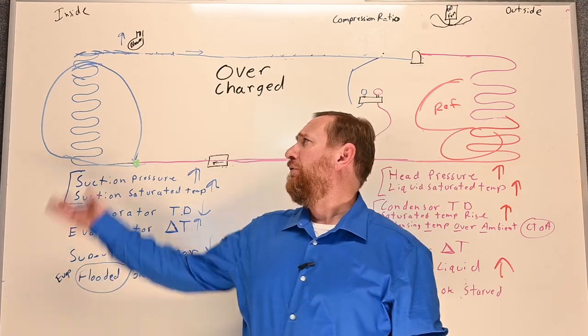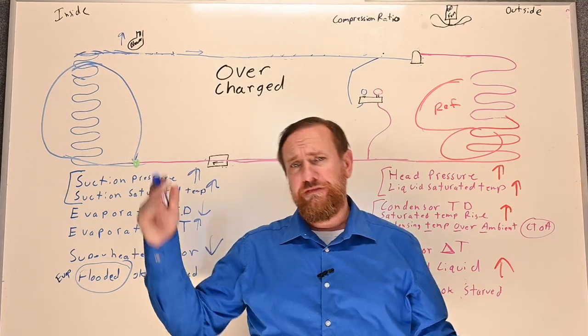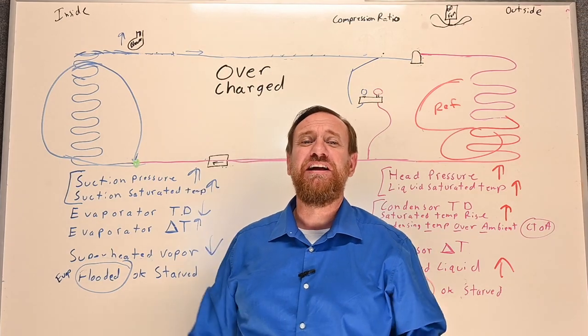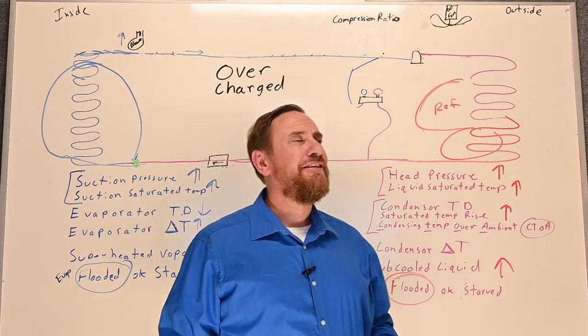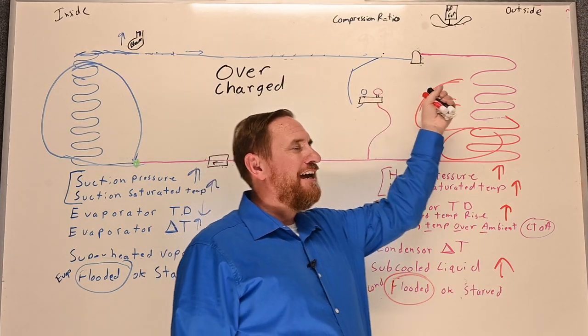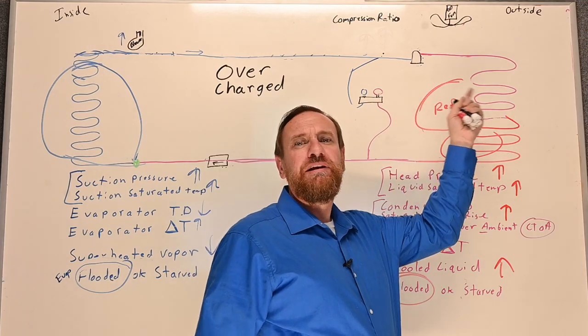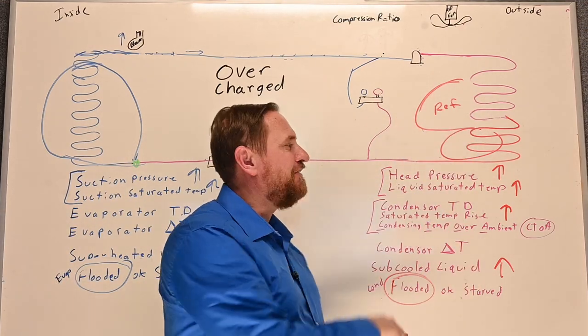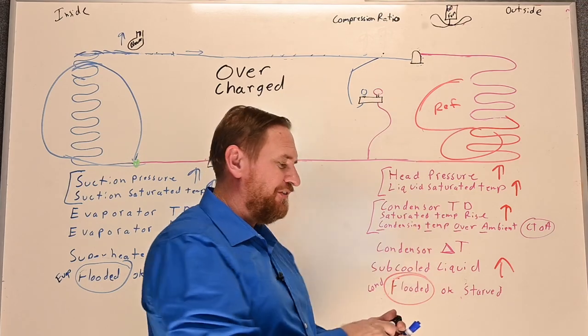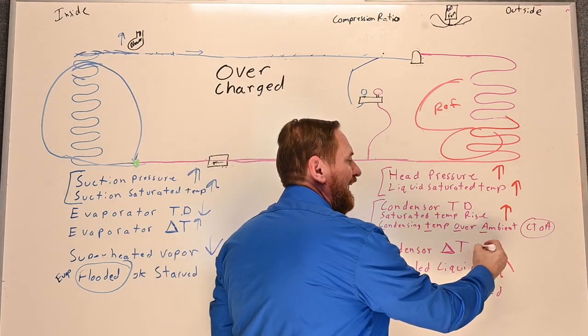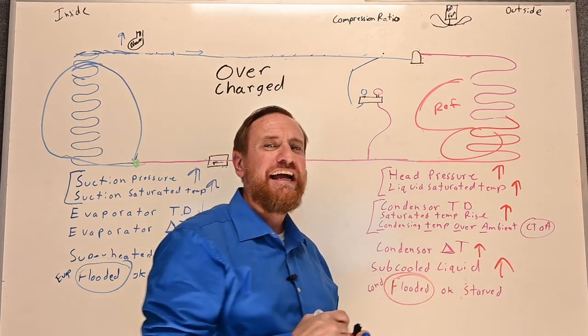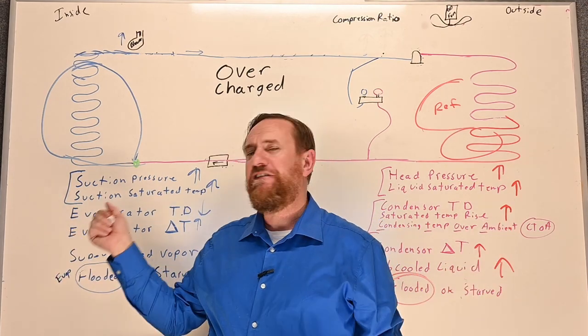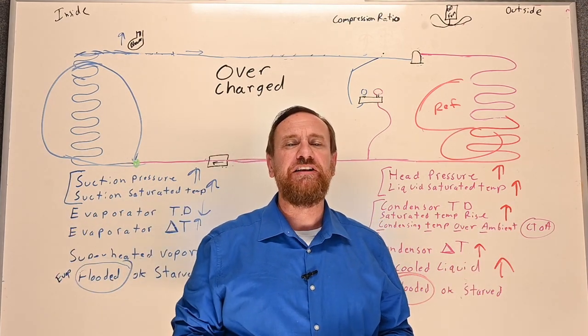You'll see people say they overcharge systems all the time and never have problems — but you're still causing damage to the customer's compressor. It doesn't happen right away, but it's still happening. We're absorbing more heat inside and rejecting it outside, which exaggerates all these issues, and you'll typically see a higher condenser delta T on the outside. That's how an overcharged system is going to affect a fixed orifice metering device.